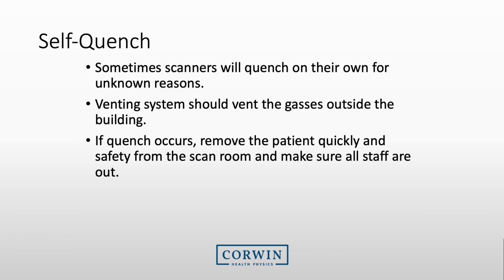Sometimes scanners will quench on their own for unknown reasons. Safety systems are in place to adequately vent the gases. If the quench does occur spontaneously, remove the patient and make sure all staff are out of the MRI room.